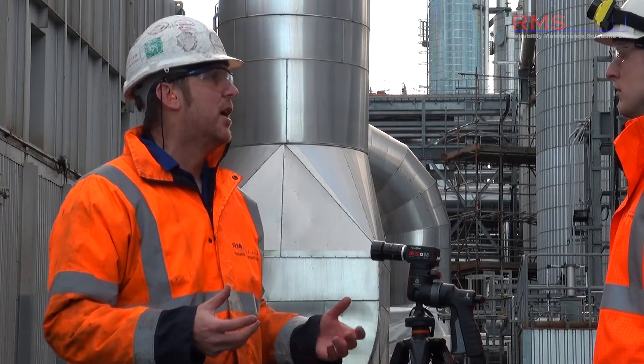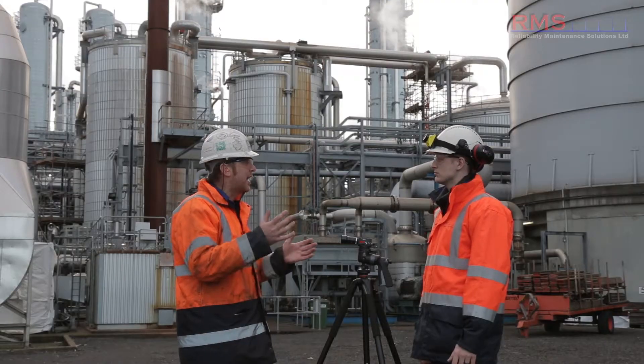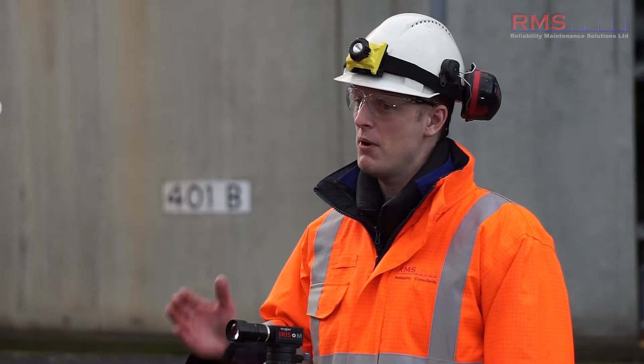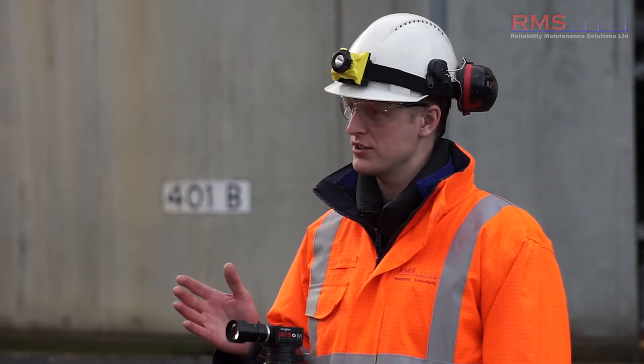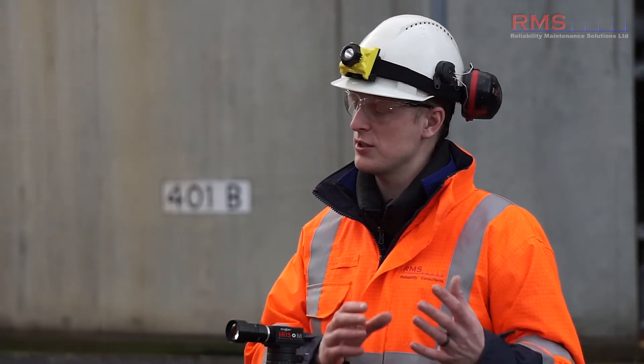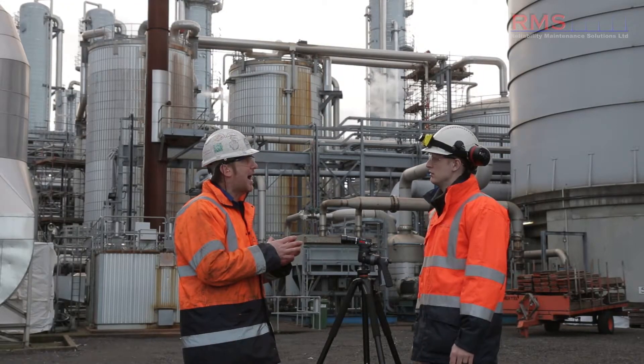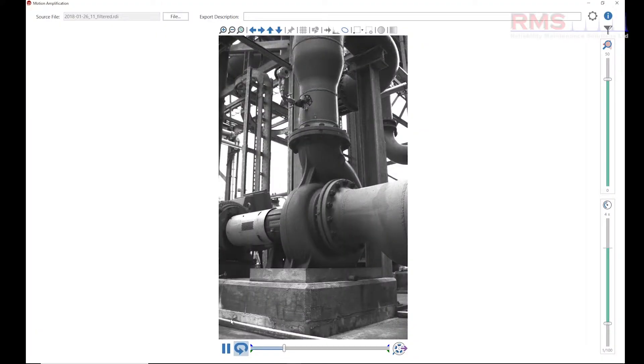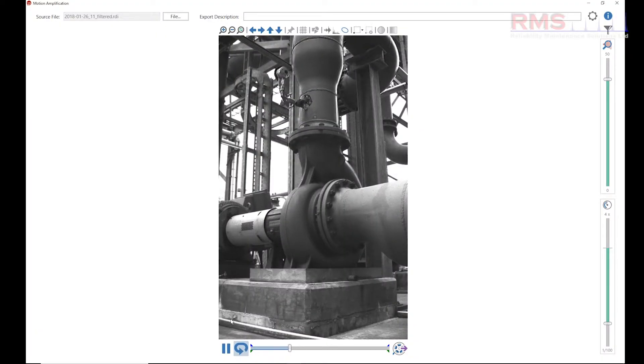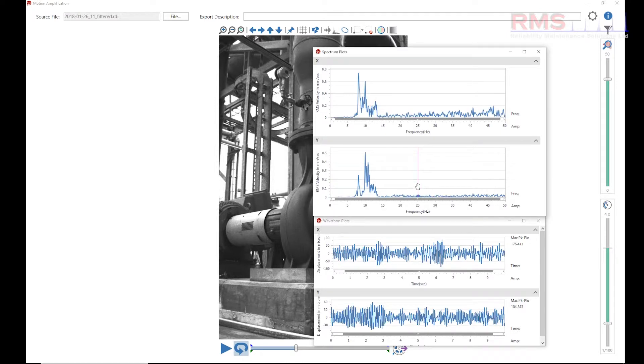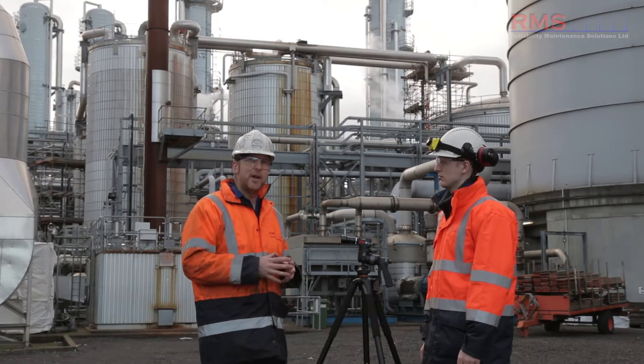What about frequency ranges — how do we adjust that? Can we look at high and low frequencies? Our F-max at the moment is up to 650 Hz, and it really excels at lower frequencies, going from zero upwards. If you wanted a higher resolution spectrum, you simply take a longer reading. Most readings are around three to six seconds, but if you want a really defined peak or to split some peaks, you just take a longer reading.